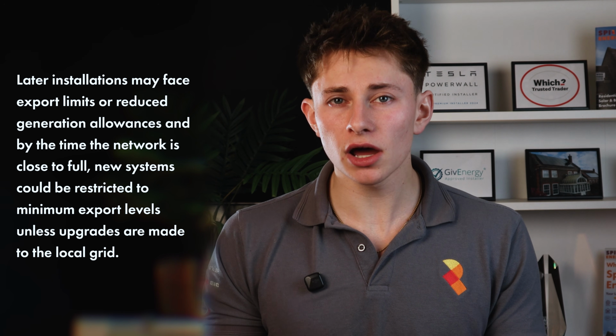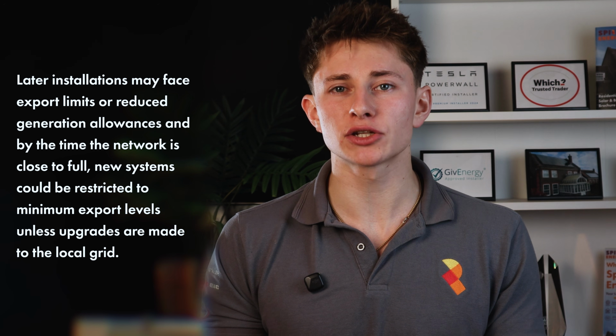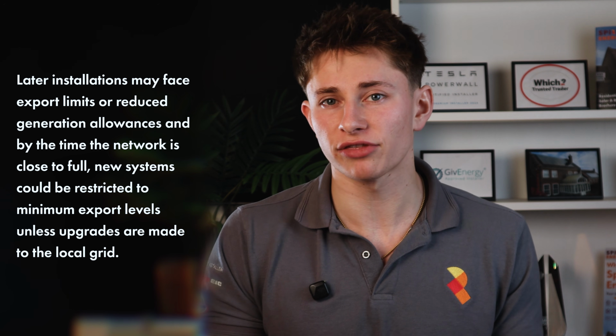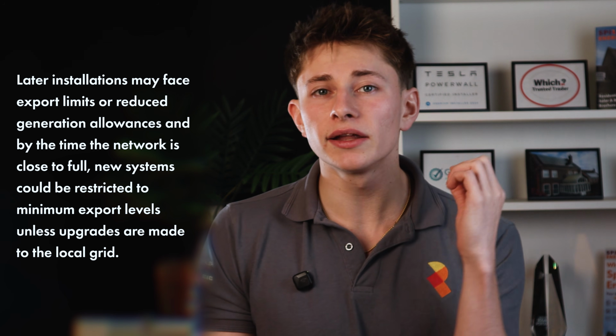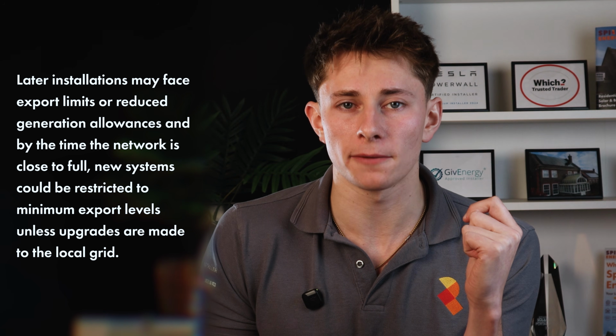By the time you get to the last few houses, they might only be allowed to install the minimum export allowance of 3.68 kilowatts unless they pay for local network upgrades. In the Berkshire area, which is where our office is, 8 out of 10 houses will get at least 11 or 12 kilowatts of generation, but often with an export limit of about 7 or 8 kilowatts. There are some areas where the grid is especially weak and some areas where it's very strong. Often you just need to apply and find out what you're allowed to install.